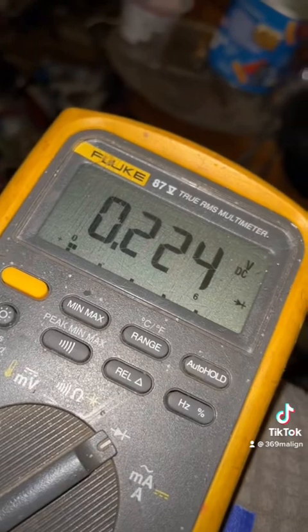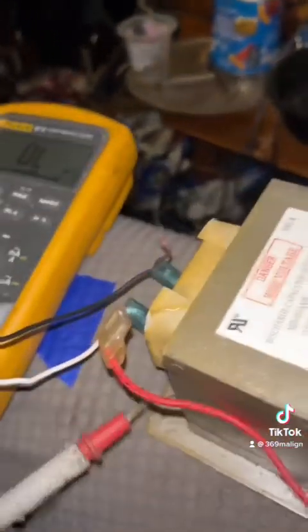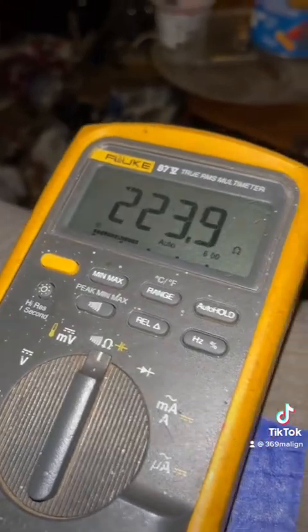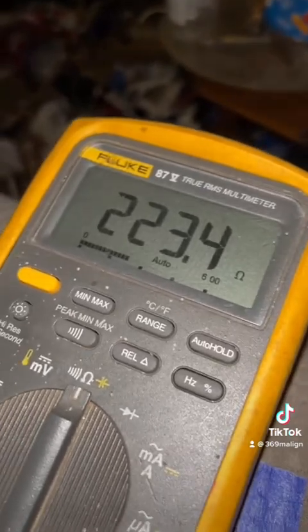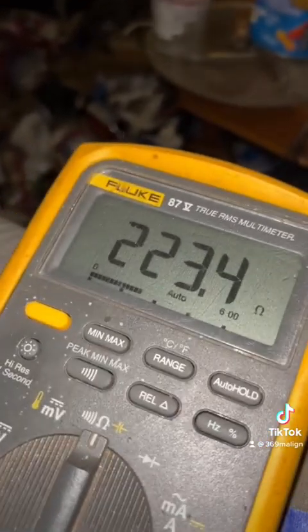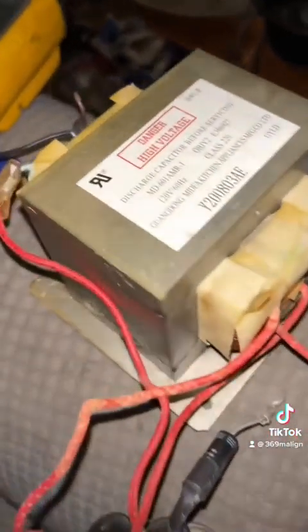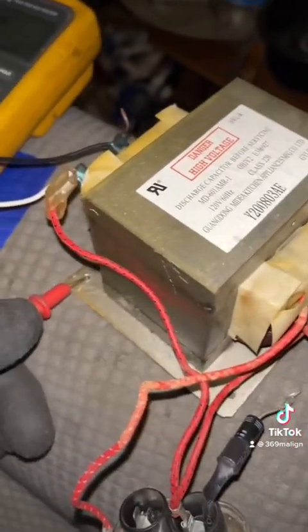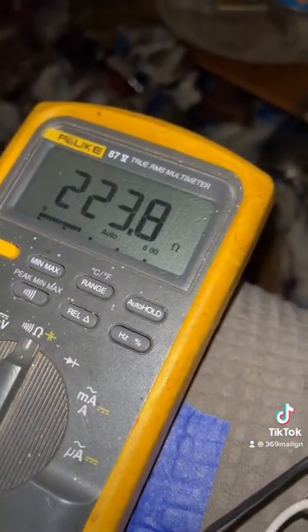Oh no. Maybe it's got some... yes, we have continuity. On this, since it's such a big winding, you're going to see more like an ohm reading than just a simple continuity tone. You want a very high ohm rating on the secondary, and this is a good ohm rating - should be somewhere between 200 and 300, I'd think. So we're looking pretty good so far. I think this is a good transformer. Yes, I'm going to say yes.